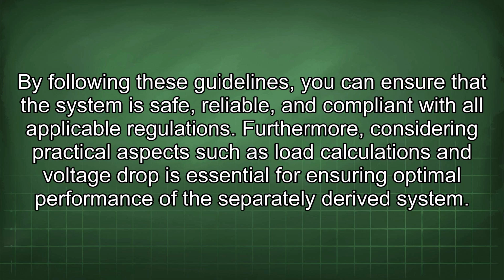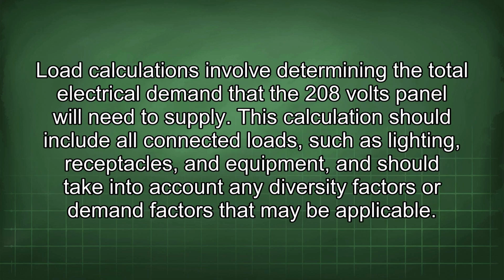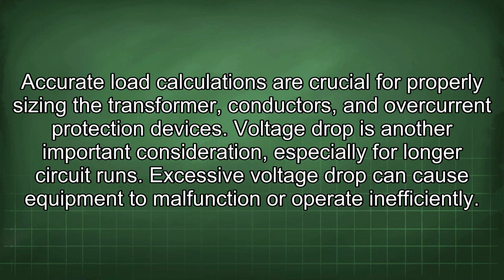Furthermore, considering practical aspects such as load calculations and voltage drop is essential for ensuring optimal performance of the separately derived system. Load calculations involve determining the total electrical demand that the 208 volts panel will need to supply. This calculation should include all connected loads such as lighting, receptacles, and equipment, and should take into account any diversity factors or demand factors that may be applicable. Accurate load calculations are crucial for properly sizing the transformer, conductors, and overcurrent protection devices.